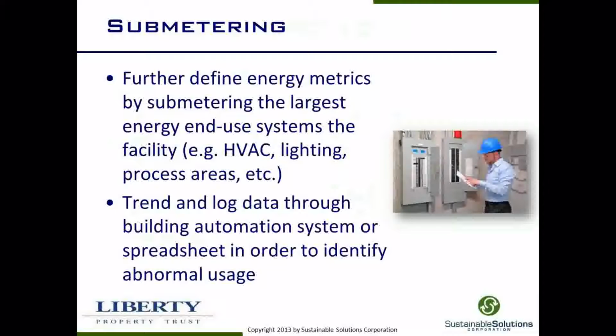I mentioned submetering earlier, and submetering allows us to really understand how energy is used in a building. Ideally we want to know energy use in the building, but even better, it's great if we can understand how much energy is used for heating, ventilating, and air conditioning, for the lighting, or the process areas. Submetering, whether it's individual circuits, allows us to really understand that. We can look at pie charts, and I'll show you an example in a little while, but being able to understand where the energy is being used allows you to effectively establish a good energy efficiency program. You can then trend and log data through either the building automation system or a spreadsheet.